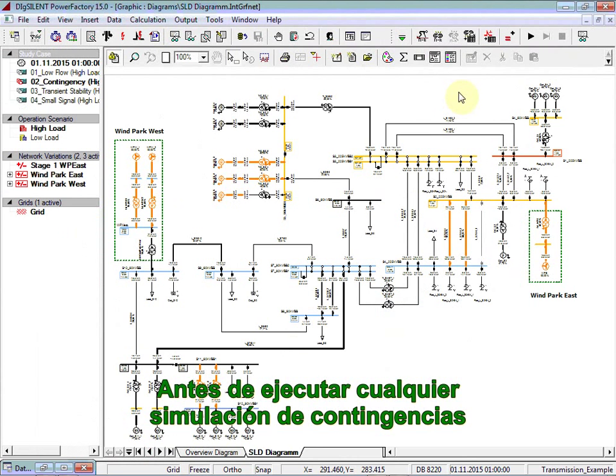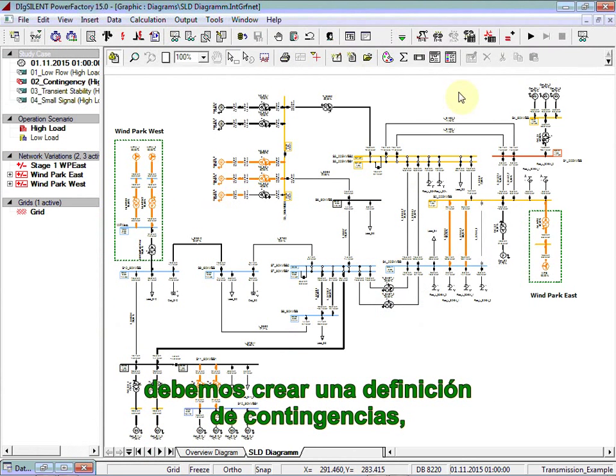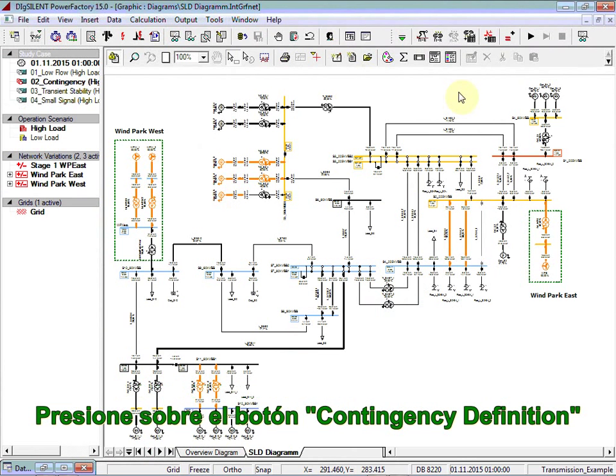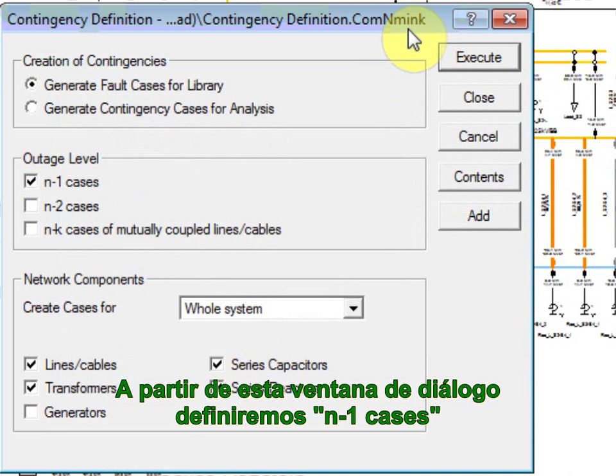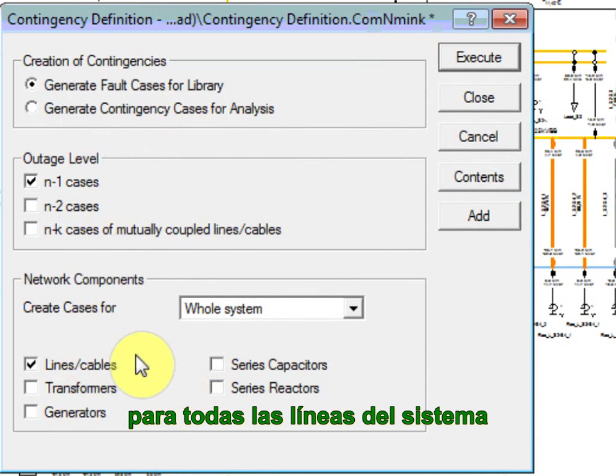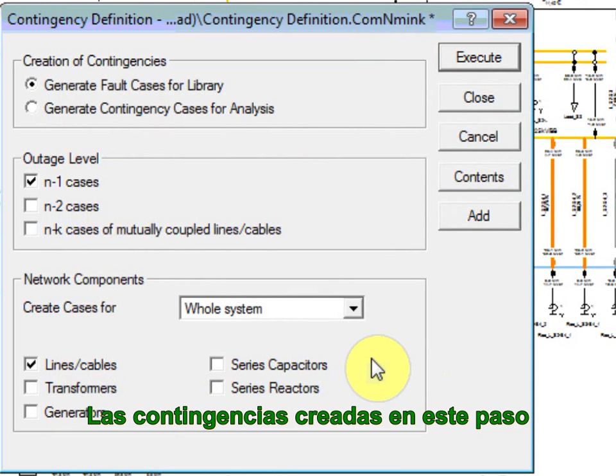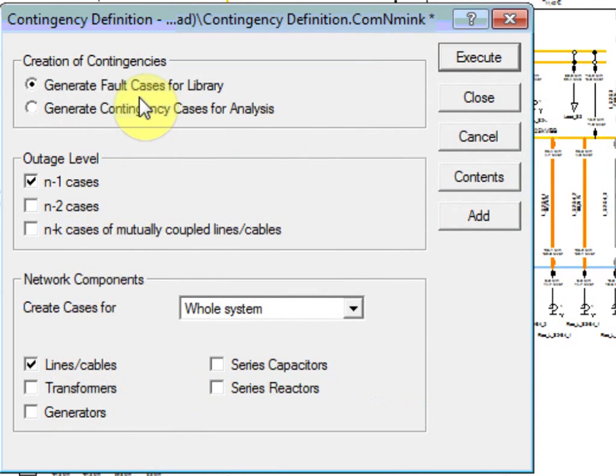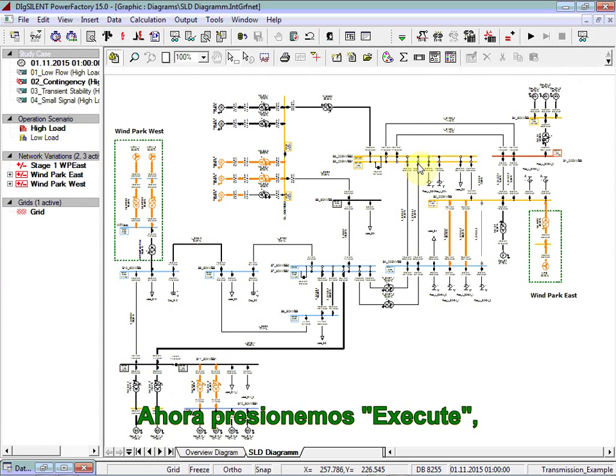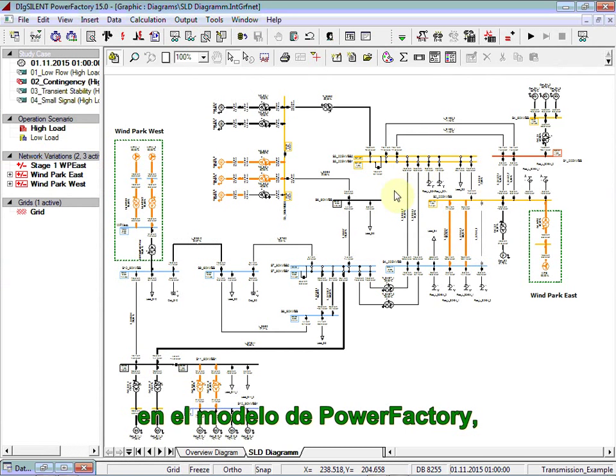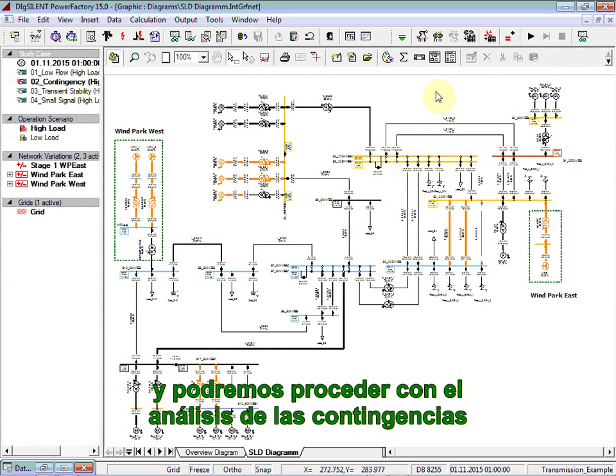Before we run any contingency simulation, we must create a contingency definition, which is a list of the elements to be outaged. Therefore, click on the contingency definition button. From this dialog, we will define N-1 cases for all the lines of the system. The contingencies created in this step will be generated in the fault cases folder inside the library. Press execute. The list of contingencies are now created inside the PowerFactory model, and we can proceed with the analysis.